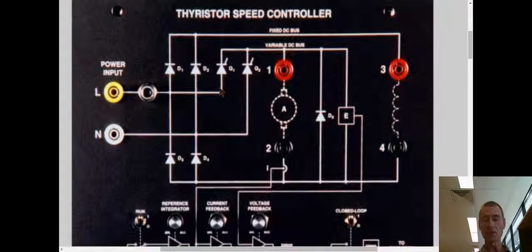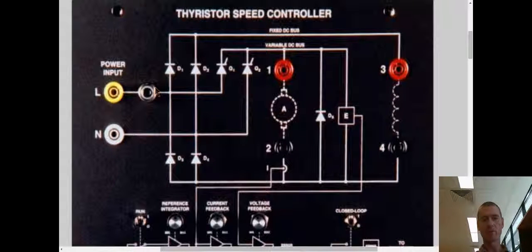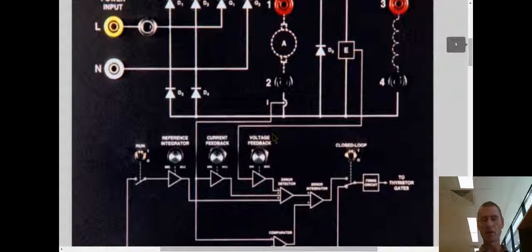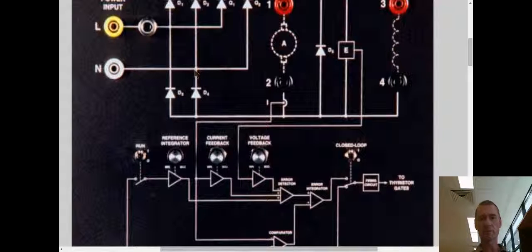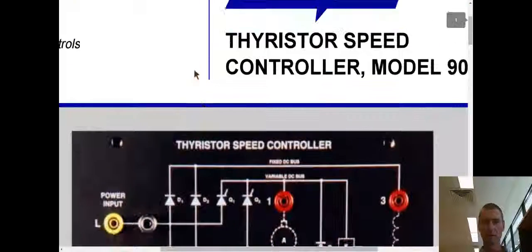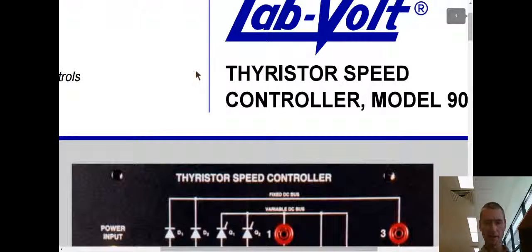Now, just an added thought, this little circuit breaker and the mains power supply breaker can trip quite a lot. This thing, if it's not tuned right, can be quite unstable and the current can wildly fluctuate, which can easily cause this breaker and the breaker on the mains power supply to trip. And that's all I wanted to say about that one.